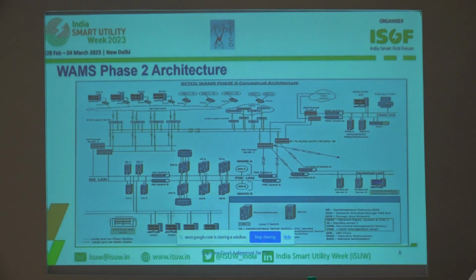Data from the PMU will come through our GETCO's fiber optics network. We have laid around 10,000 kilometers of OPGW at present, and 7,000 kilometers are in the pipeline. So 70% of the grid is connected through our GETCO FOT network, OPGW network, and the rest 30% of data is coming through lease line or some other communication medium.